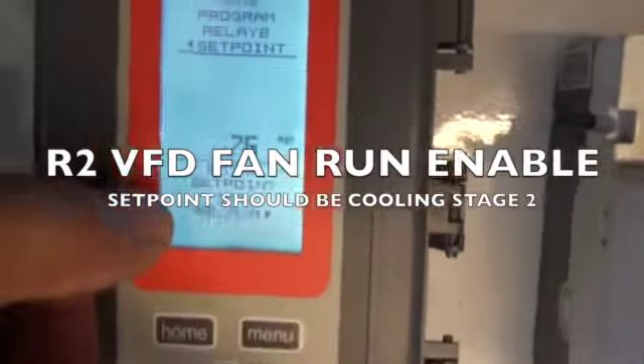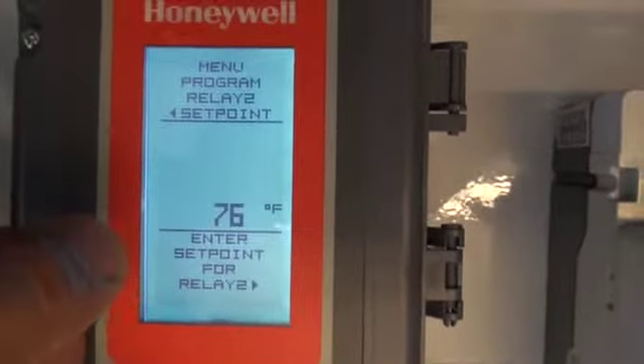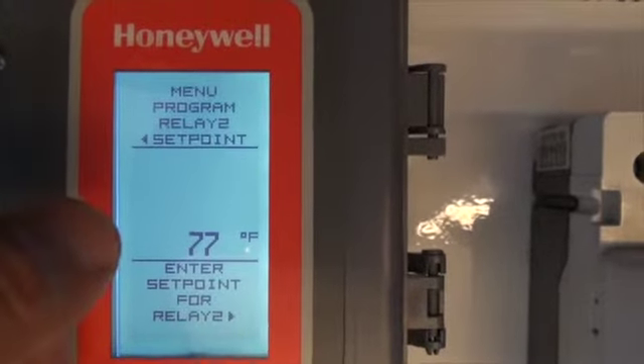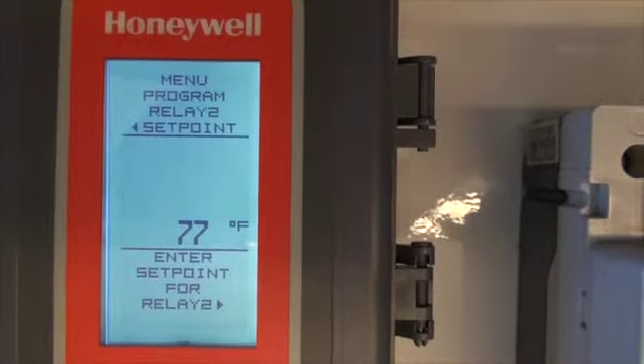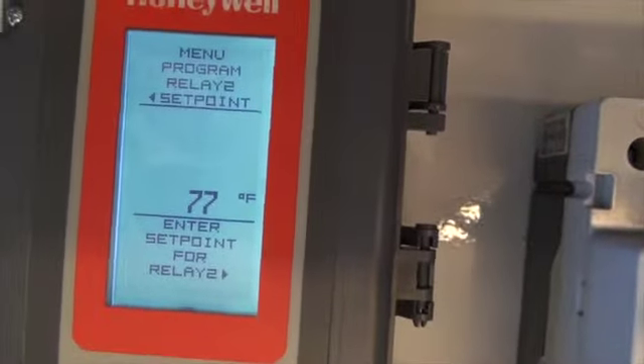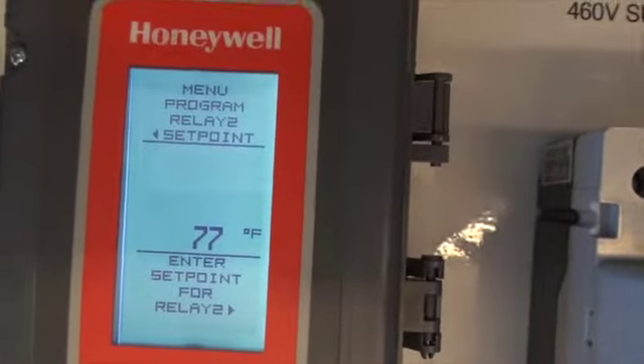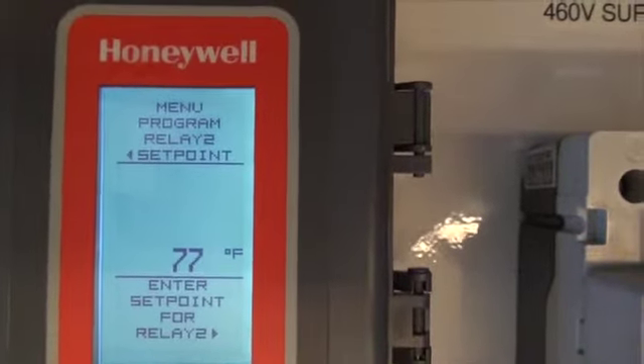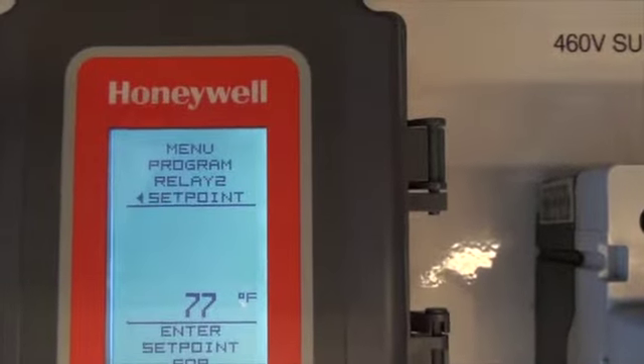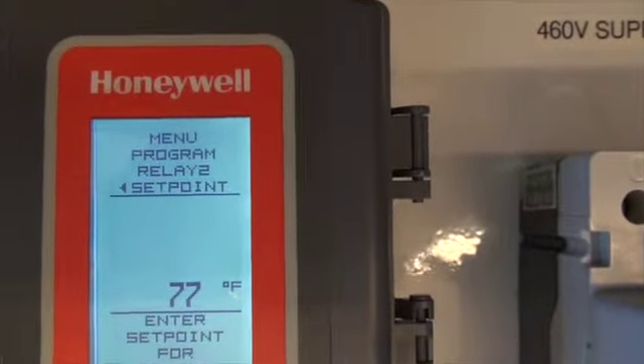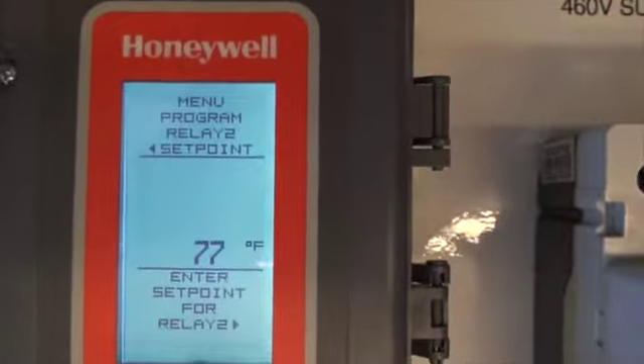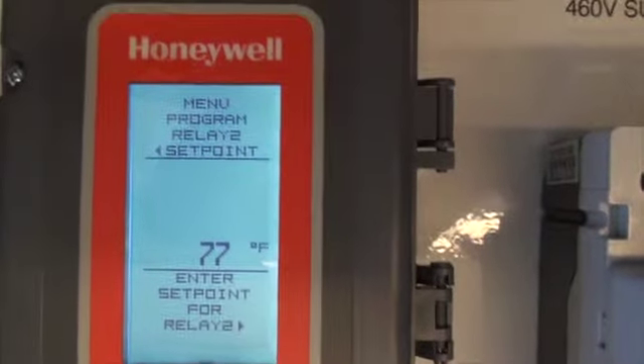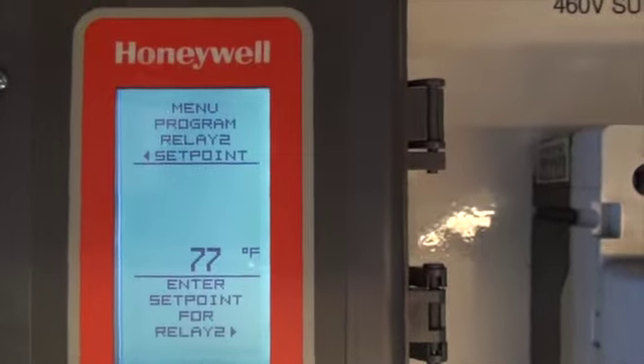Relay 2 set point needs to be set higher than the spray pump, so I like to set that at 76 or 77 degrees. Have about a 2 degree spread between the spray pump coming on and the enabling of the VFD to run forward. Remember that we set the modulation output, the ramping of the drive up and down, at 80 degrees. This 77 degrees is where you want the drive to start run forward.